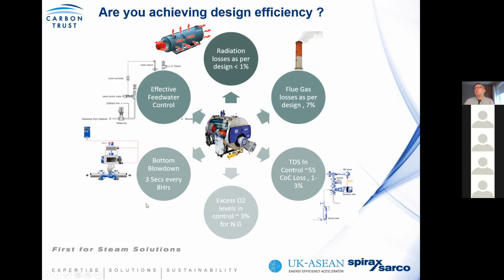You also have the bottom blowdown. We find that some companies use their bottom blowdown as a means of controlling conductivity in the boiler. This doesn't work effectively, and you're basically blowing down a lot of water with poor control of TDS. So it's more effective that the bottom blowdown operates for what it's designed for, and you should only operate it for 3 seconds every 8 hours. The function of the bottom blowdown is simple. The rapid operation of a blowdown valve creates a kinetic internal shock in the boiler to allow you to resuspend settled sludge, so that it gets removed more effectively by your surface or TDS blowdown. It is not designed to control TDS.